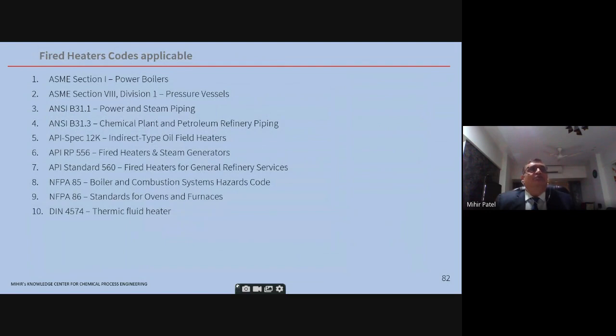Fire heater codes applicable: these are the various codes applicable for a fire heater. API Standard 560 is for fire heaters for general refinery services. There's DIN 4574 at the bottom, which is normally used for small hot oil heaters. It is roughly 30-40% cheaper than an API heater, which is a very large heater.